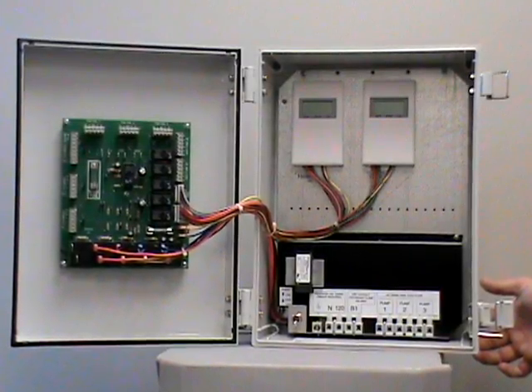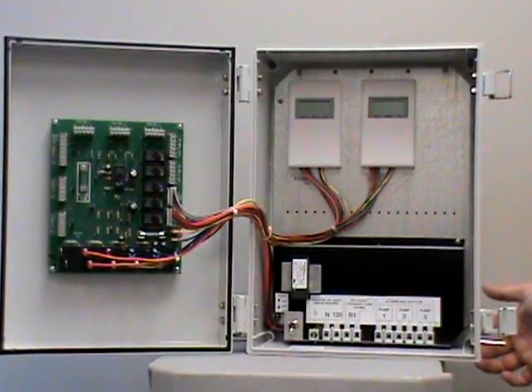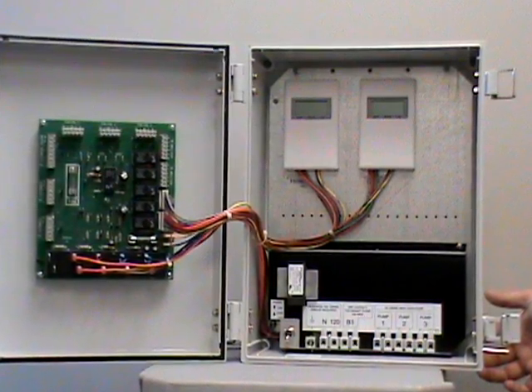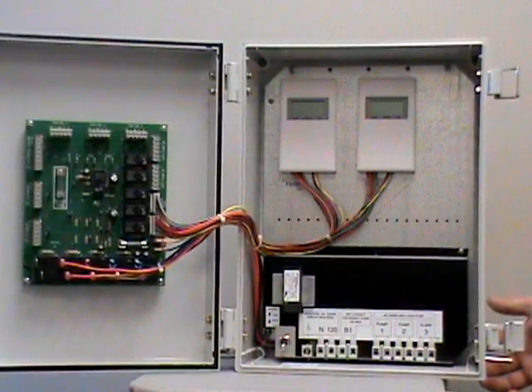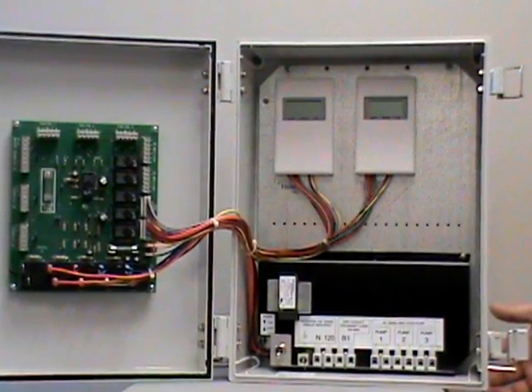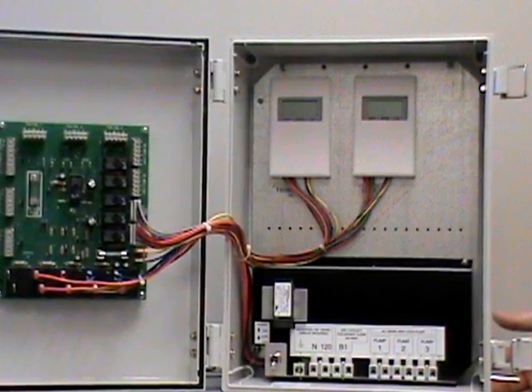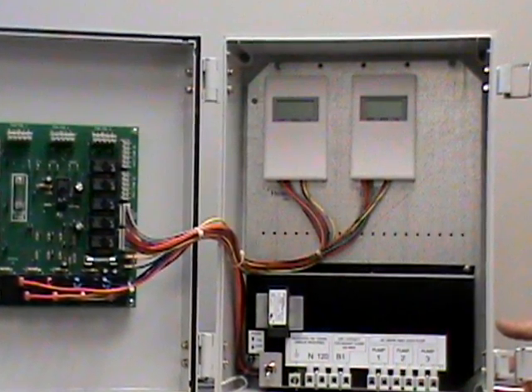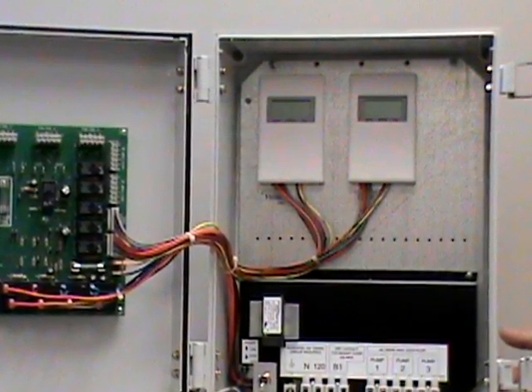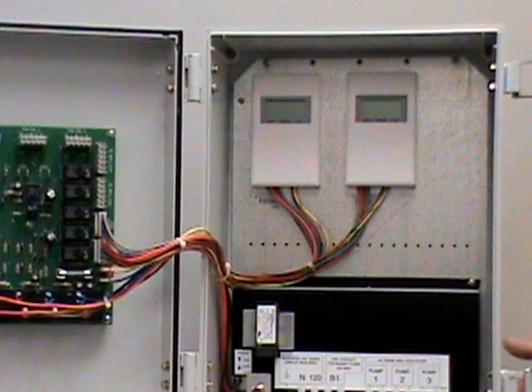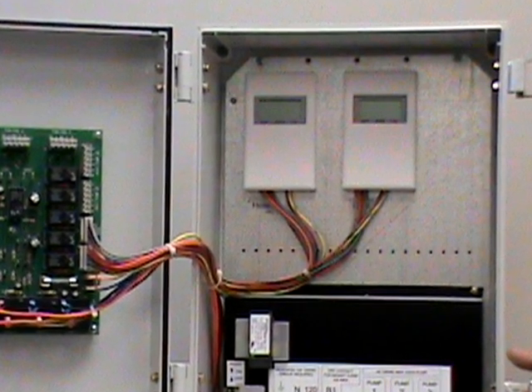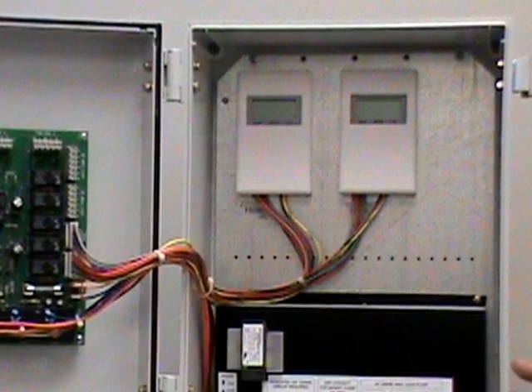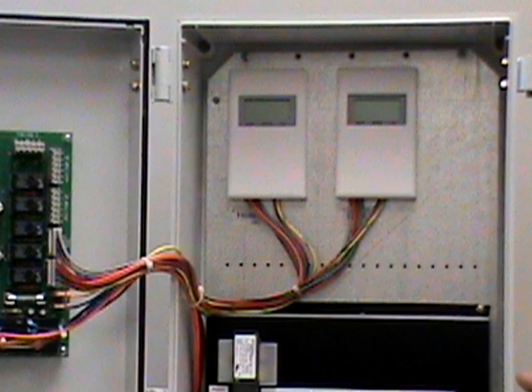Inside the hydronic control module, there are 2 set point controllers. The left controller is active in the heating mode, and the right controller is active in the cooling mode. They are programmable 2-stage controllers used to monitor the buffer tank temperature and start and stop up to 2 heat pumps or 2 compressors or 1 heat pump and a backup boiler.